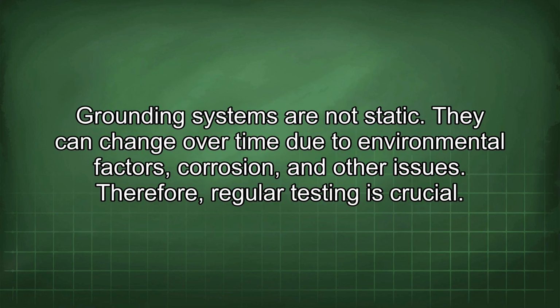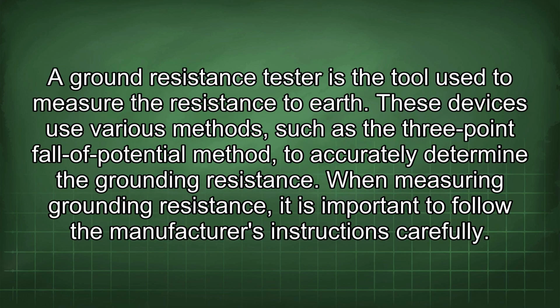Grounding systems are not static. They can change over time due to environmental factors, corrosion, and other issues. Therefore, regular testing is crucial. A ground resistance tester is the tool used to measure the resistance to earth. These devices use various methods, such as the 3-point fall of potential method, to accurately determine the grounding resistance.